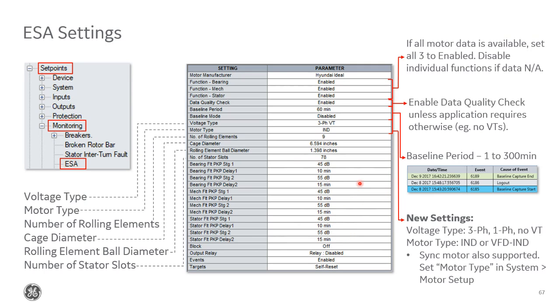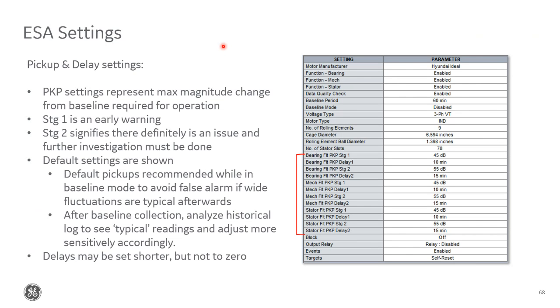So in terms of setting, aside from putting in your motor information, there's really not anything that you need to calculate. It's very simple to set up. This is all you need to do. Once you enable all of this, the relay will go to work, and you just need to take a look at the metering screens once in a while and see what's going on. So basically, this was just explaining those pickup settings.